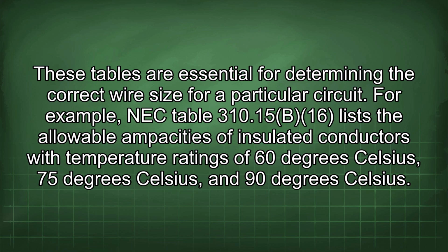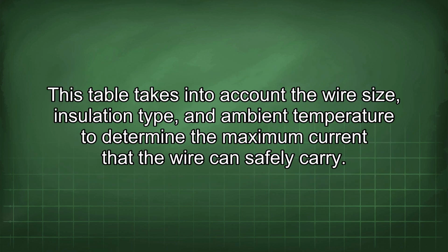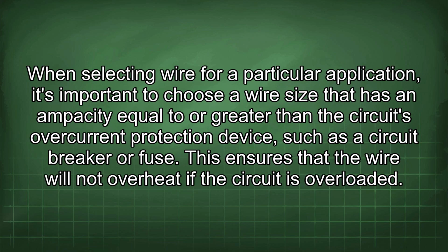For example, NEC Table 310.15(B)(16) lists the allowable ampacities of insulated conductors with temperature ratings of 60 degrees Celsius, 75 degrees Celsius, and 90 degrees Celsius. This table takes into account the wire size, insulation type, and ambient temperature to determine the maximum current that the wire can safely carry. When selecting wire for a particular application, it's important to choose a wire size that has an ampacity equal to or greater than the circuit's overcurrent protection device, such as a circuit breaker or fuse. This ensures that the wire will not overheat if the circuit is overloaded.